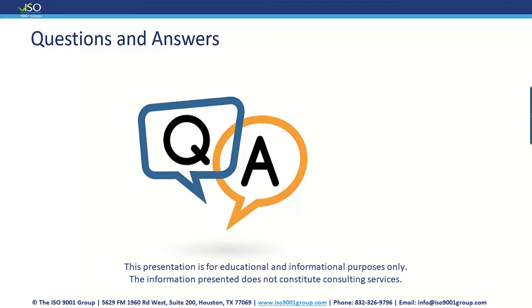All right, so hopefully I've been able to really explain in a practical way that in many cases, the equipment that you're sending out for calibration, you can save yourself a lot of money by implementing a verification program. And if it's reading correctly when you verify it, you do not need to send it out for calibration. The only time you would need to send something out for calibration is after you verify it and it's not reading properly. Send it out for calibration. And I'm sure if you do that, you're going to save yourselves a lot of money on your calibration program.